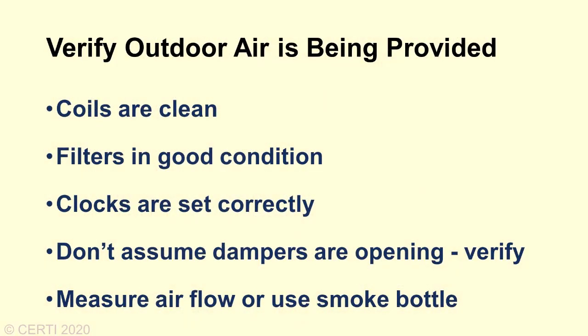More often than not, a bit of detective work will identify a problem that can easily be fixed. Start with verifying outdoor air makeup is being provided and at the right time. Coils are clean, filters are in good condition, clocks that control when fresh air is provided are set correctly. Sometimes this may mean even getting inside the air handler and verifying the dampers are truly open. Use a smoke bottle or measure the airflow directly.